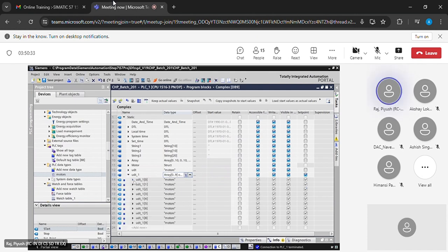There you can see in UDT 1, here I have all those parameters that I have defined. So this UDT is very helpful when you are doing faceplate type of things. When you create faceplates in SCADA, for a single instance, a single faceplate, you created a UDT, then you can use that UDT for multiple faceplates. Correct?